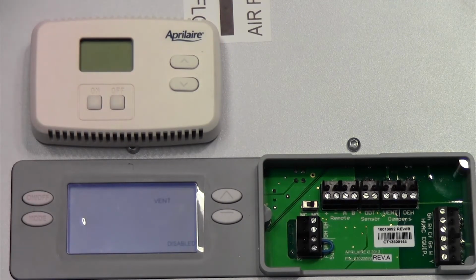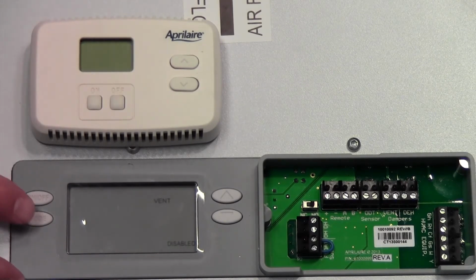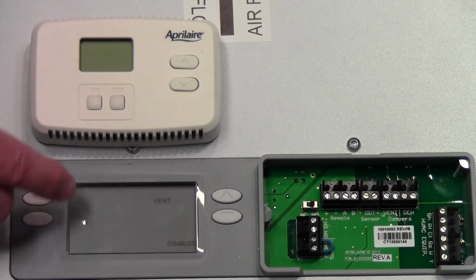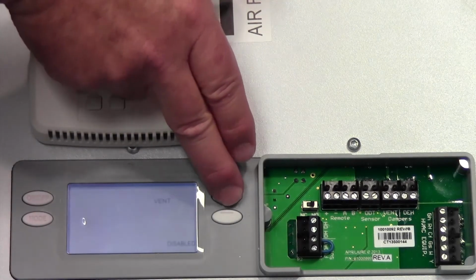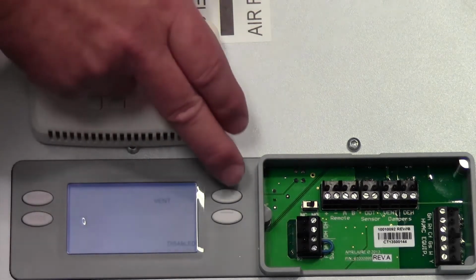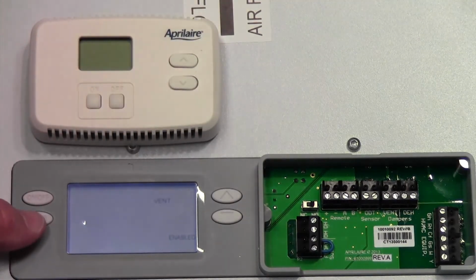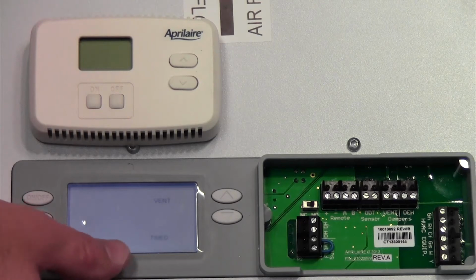This unit actually has the ability to tie in a fresh air damper from the outside. We can tie in a 6-inch or 8-inch round damper to the inlet, tee that into the inlet or wire it into the inlet, and bring in fresh air. When doing ventilation, this unit will actually open up the normally closed damper to the outside of the house and draw in air through the unit by pulling it in with its own blower and monitor that incoming air. Once we say that we want to have ventilation, the first thing it's going to ask us is if we want to do vent timed.